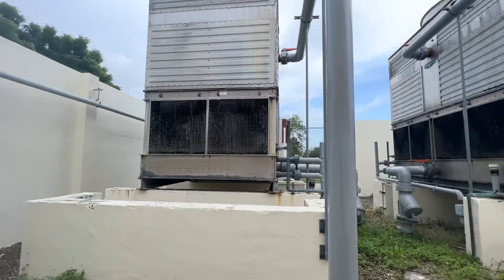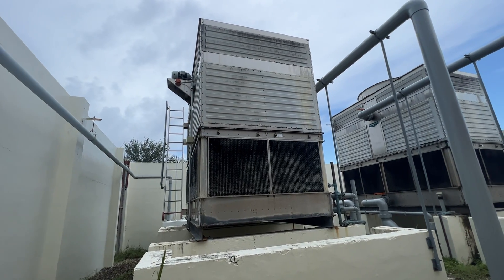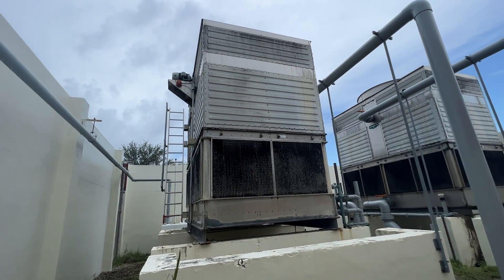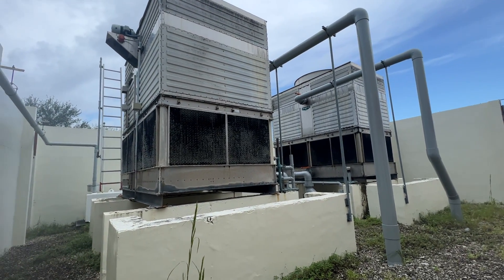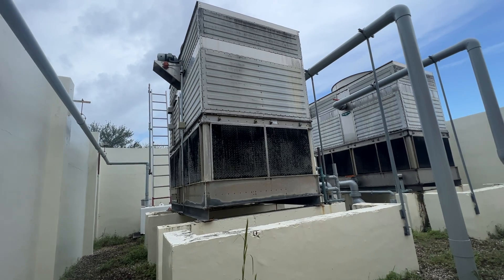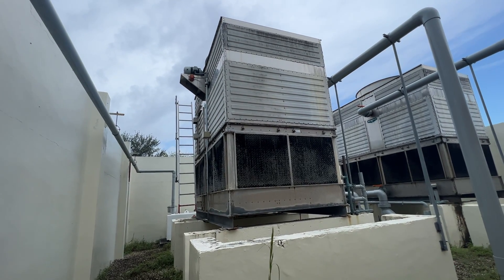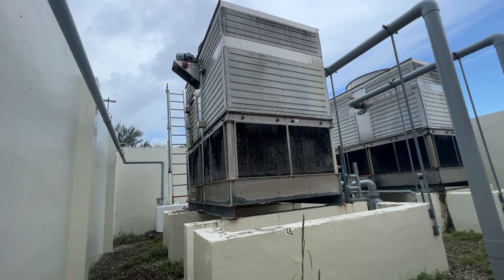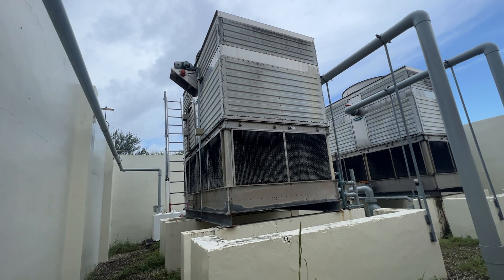It looks like we're going to be pulling new wiring over here at my disconnect. That's probably the end of this video — I'll follow up when we get the wires replaced. It seems like my motor's good, and once that chiller starts up with no air in the lines and the water piping is corrected, we should have a chiller up and going. For now, that one's carrying the building. Thanks for watching — subscribe if you haven't and want to see more videos like this.